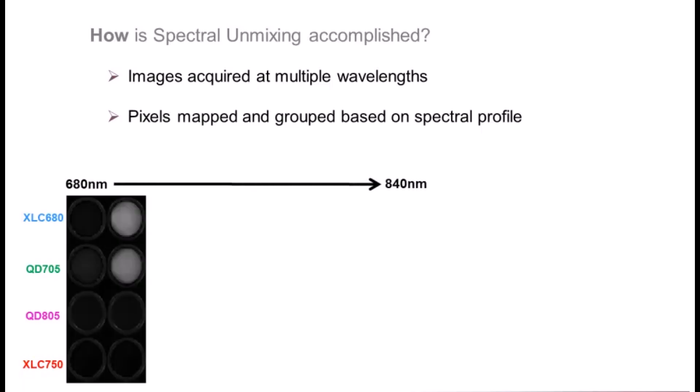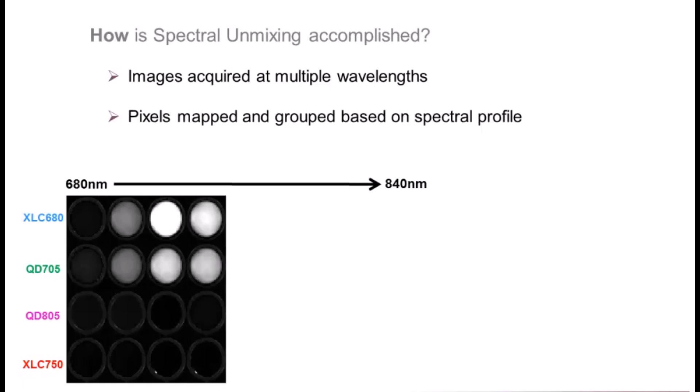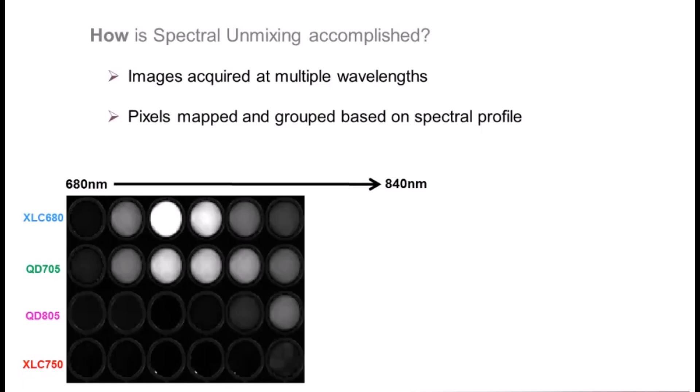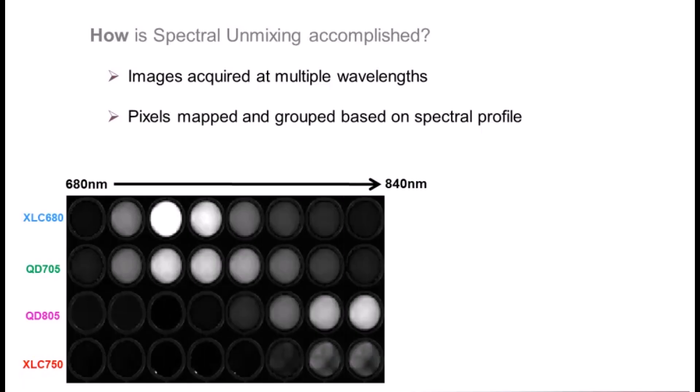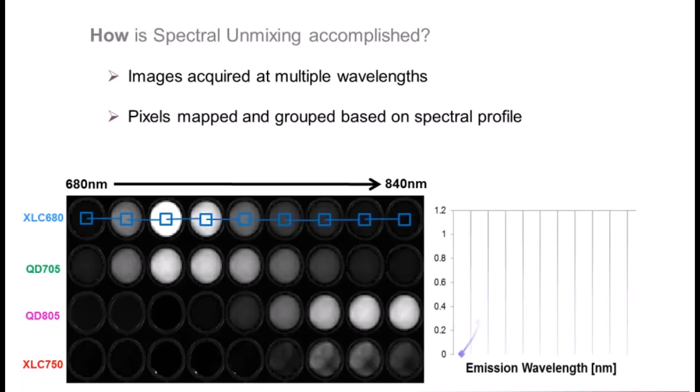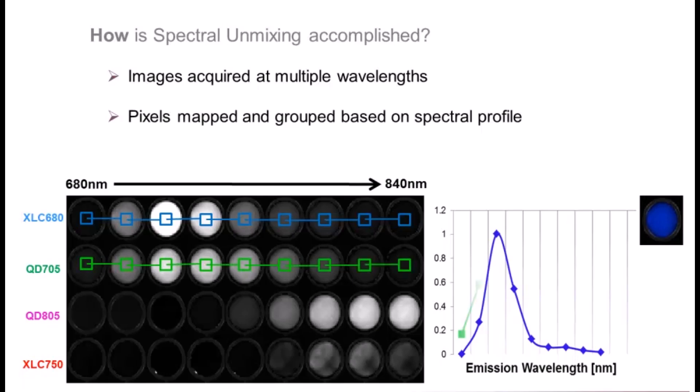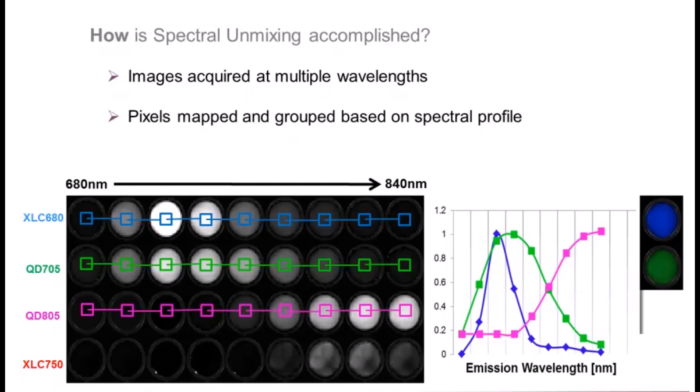To accomplish this, images are acquired at multiple wavelengths. In this case we scan from 680 to 840 nanometers. Pixels from the acquired images are mapped and grouped based on their spectral profile or signature. These grouped pixels are then separated into individual components so that accurate quantitation can be performed.